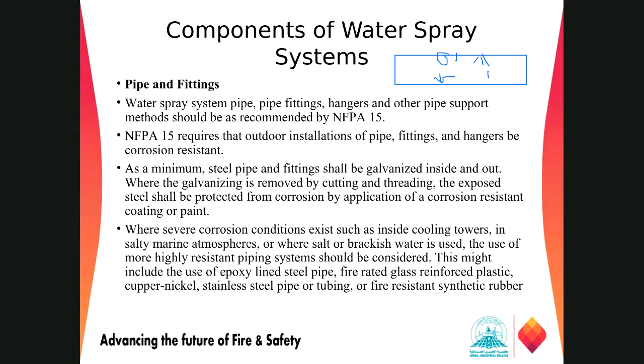I mean, if you are installing your pipe, it should be galvanized. First, you have to purchase the pipe from the manufacturer, because the pipes do not come galvanized from the factories. So we have to send this piping to the galvanizing plant, or galvanizing unit. They will put it inside a zinc bath, a molten bath, for some time, and then they will add the galvanization on the outer part and the inner part of your pipe. After some hours, you can collect your pipe for the installation.